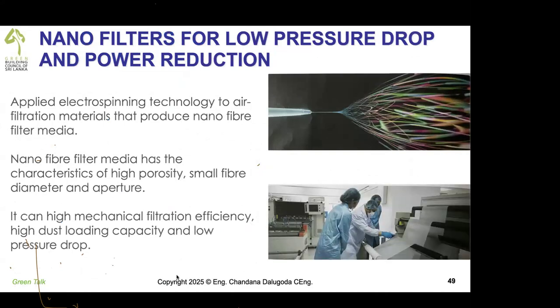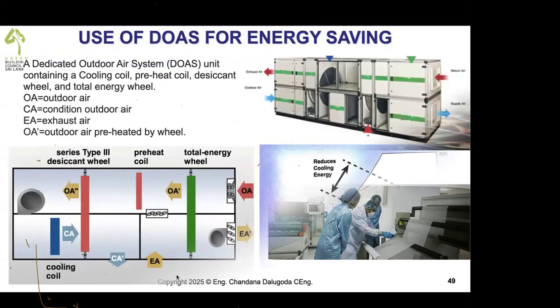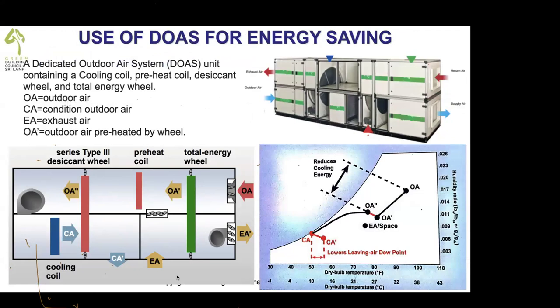Nanofilters, a latest situation. I was very fortunate. I went to Hong Kong to deliver my ASHRAE distinguished lecture last year. I was taken to a nanofilter production facility. I saw with my own eyes how it is done and how the MERV filter classification is given. With nanofiltration, pressure drops are much lower. Your AHU fan motor horsepower goes down tremendously. That is energy saving. Another way of cutting down is using DOAS, dedicated outdoor air systems. That is an air handling unit.